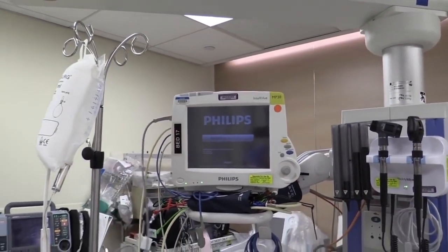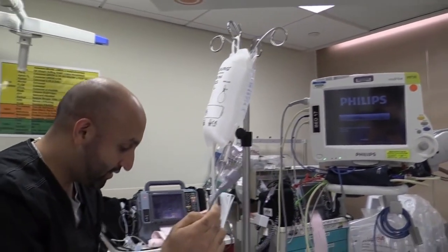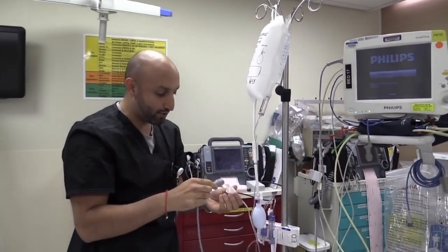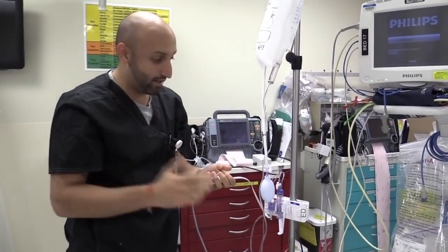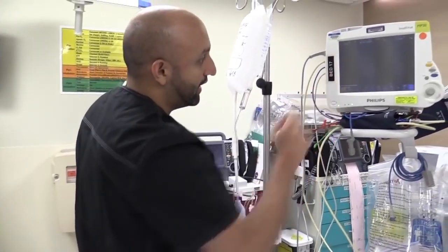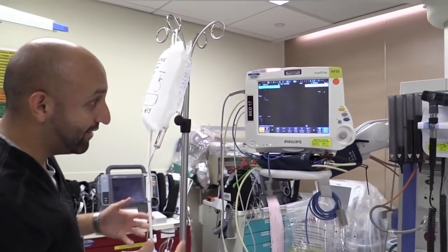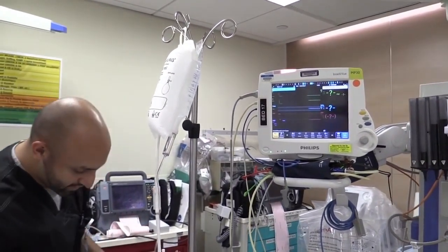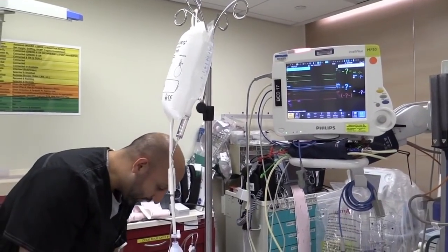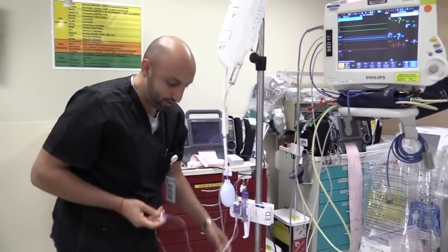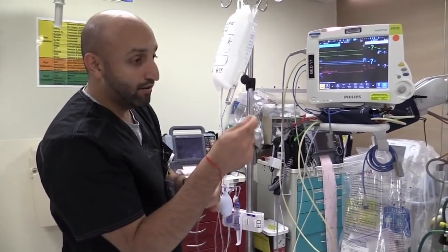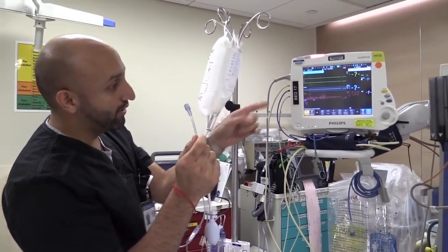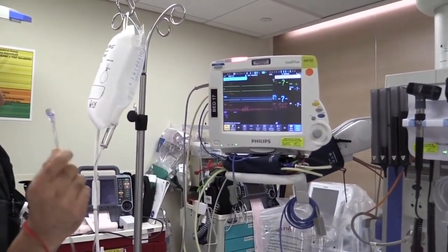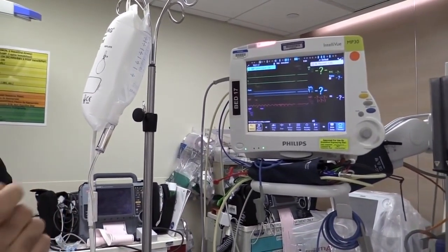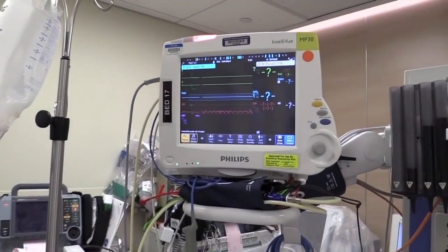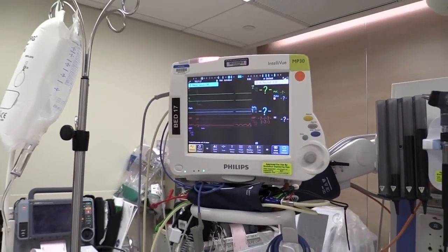The other end, essentially right here, is just going to go and connect right onto the actual arterial transducer itself, and that clicks in very easily, and now our monitor is on. So if this is actually connected appropriately, if you take the part that goes into the patient, which is right here, and you wave it around, you should see on the monitor a little bit of artifact. That means everything is hooked up and connected correctly. Alrighty, so that's the second part, is getting all the air out of the IV tubing.